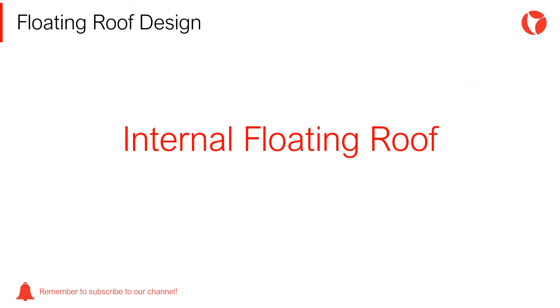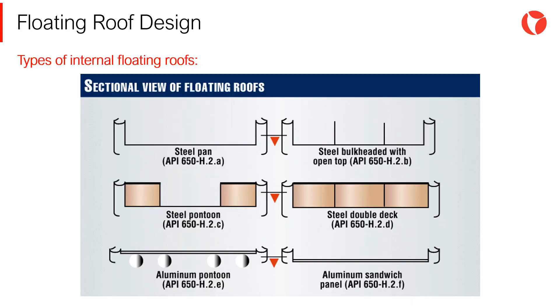Internal floating roofs are used inside fixed roof tanks to reduce gas emissions. Since this type of roof is not in direct contact with the atmosphere, its construction is much lighter compared to external floating roofs. The requirements for internal floating roofs are limited only by safety and durability factors. Allowed configurations and minimum requirements are included in Annex H of the API 650 code. There are different types of internal floating roofs as shown on the screen, going from bulk-headed type and steel pontoon type to aluminum sandwich type.